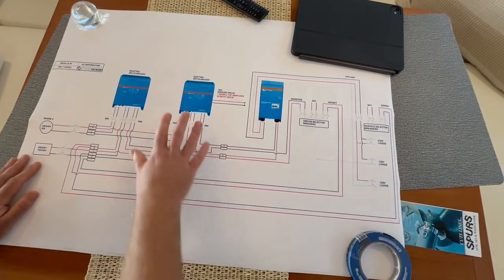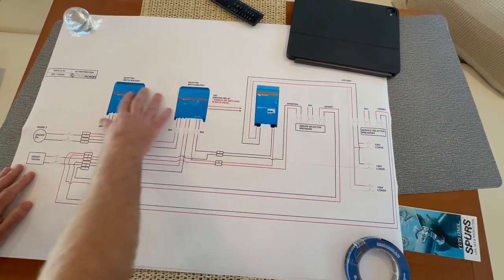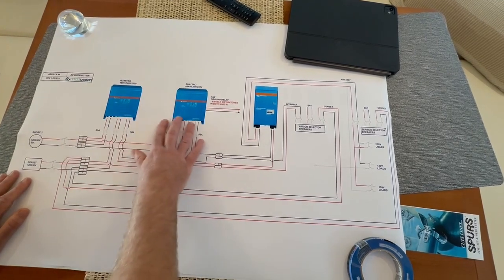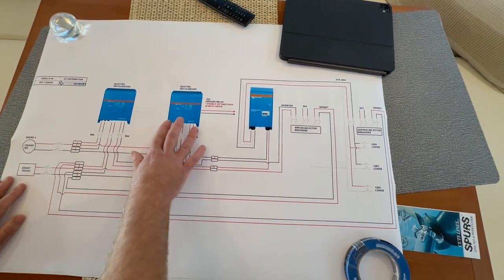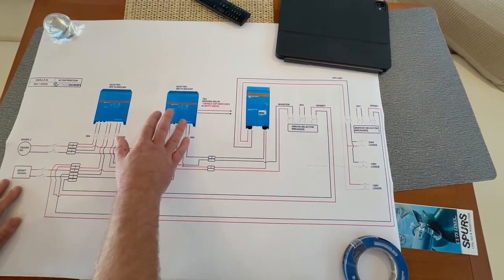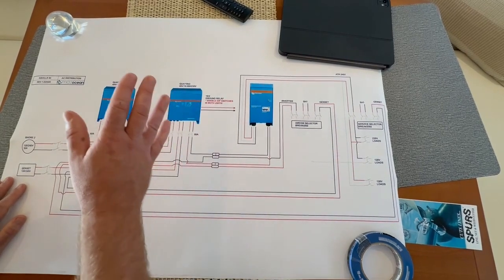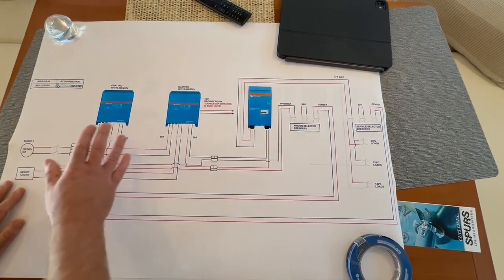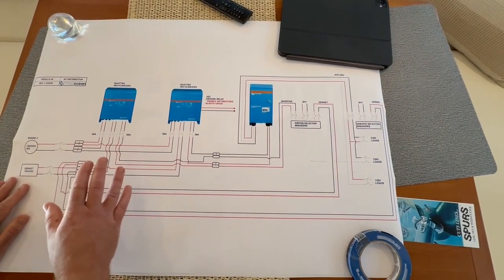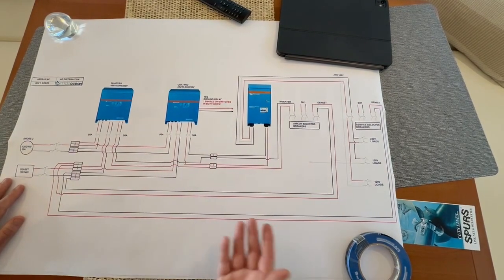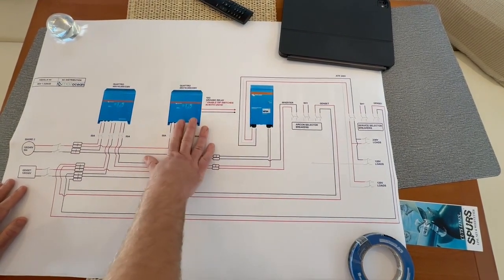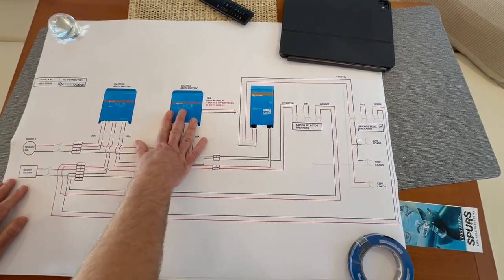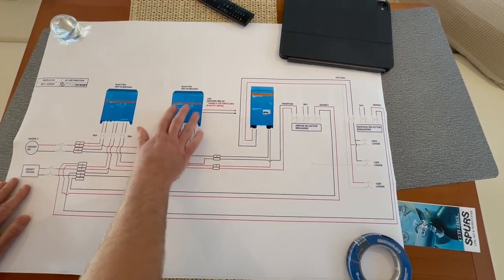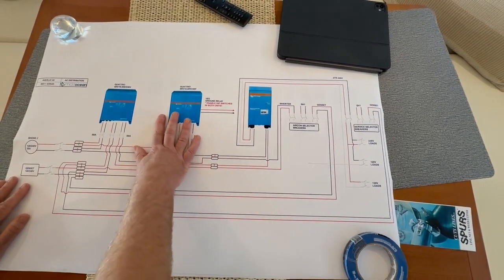With the Quattros, that's all built in, part of the Victron Quattro system. They automatically detect and make those decisions and changes by themselves. Where we engineered here was that we created a bypass scenario, because the most likely thing to fail in the system would be one of these Quattros. And if you lost them with no way to bypass, you're basically dead in the water.